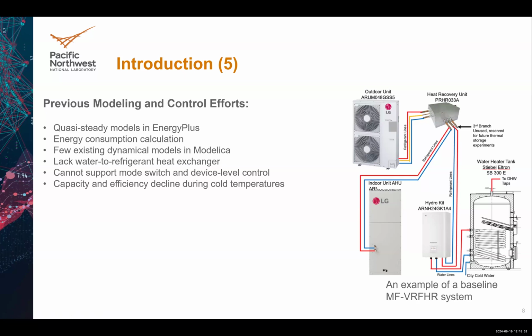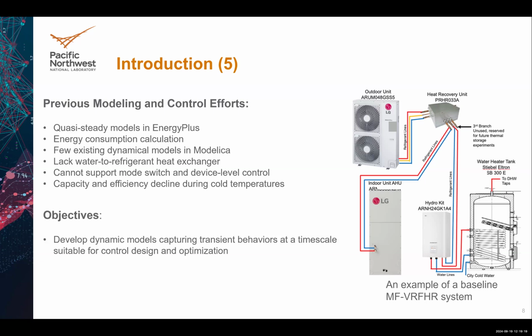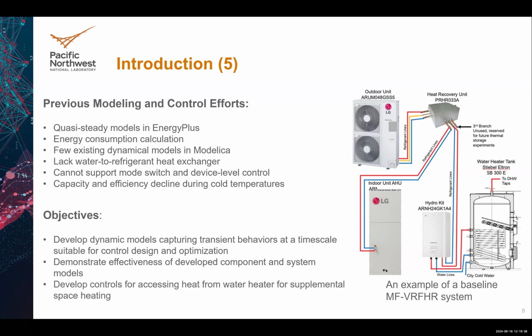In terms of controls, usually the models cannot support mode switch and device level control. We have several operation modes, right? But the available models cannot support the mode switch and the device level control. In addition, the capacity and the efficiency of these models will decline during cold temperatures. So the objectives of this study: first, we try to develop dynamic models capturing transient behaviors at a time scale suitable for control design and optimization. Also, we want to demonstrate the efficiency of the developed models. Lastly, we develop some controls to extract heat from the water heater for supplementary space heating.